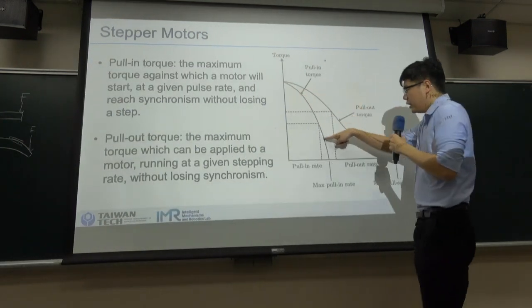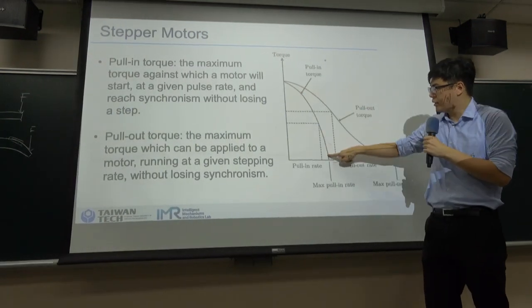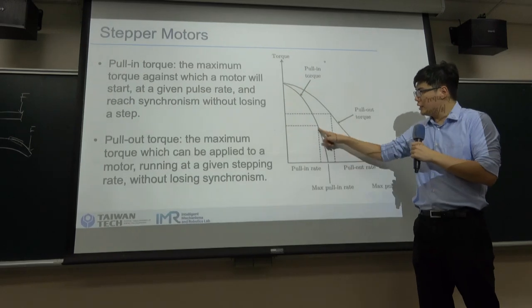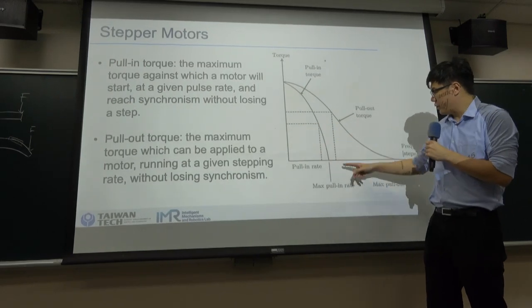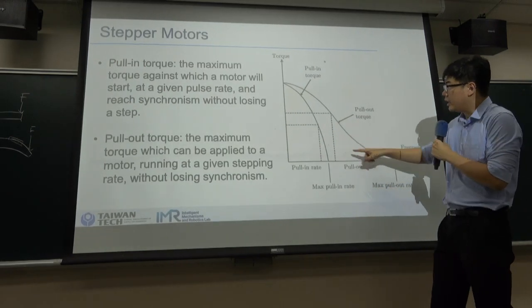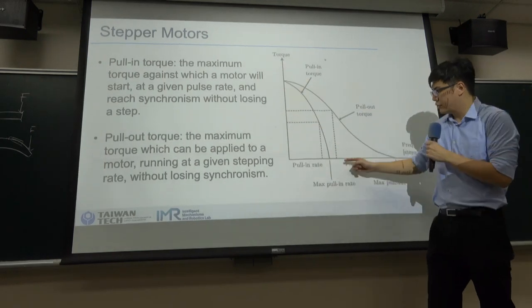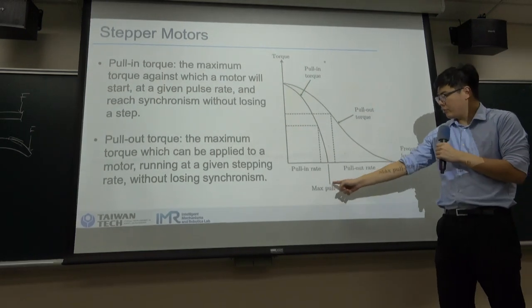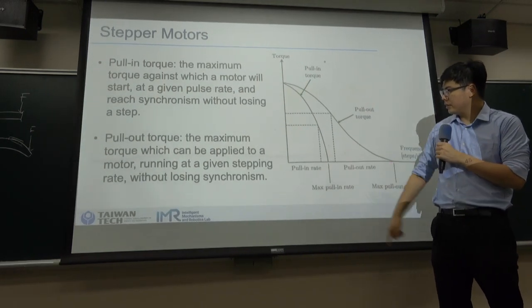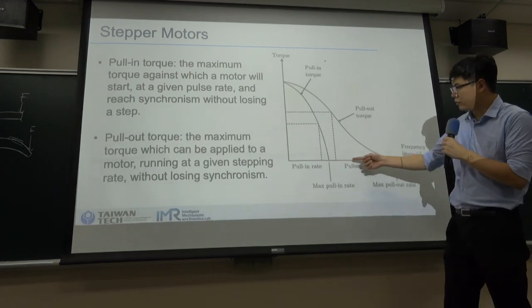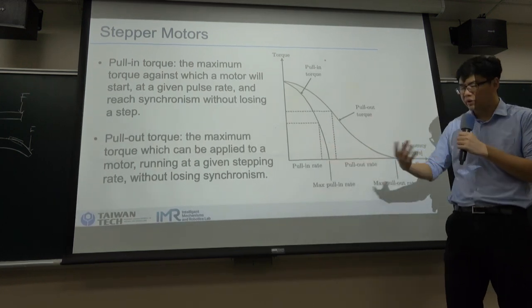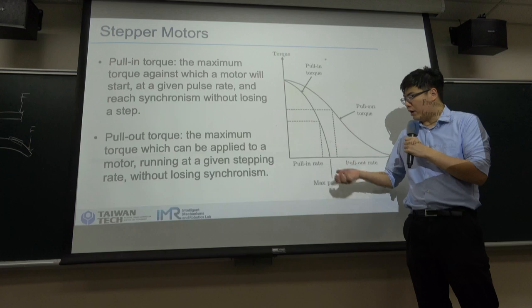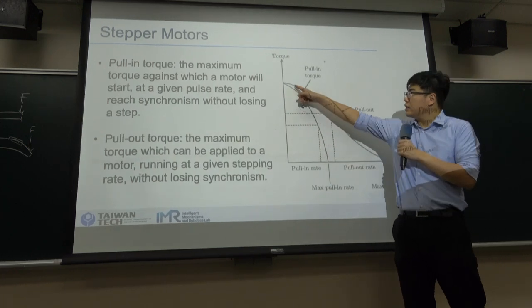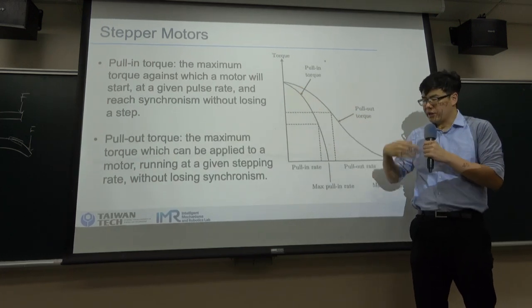You can see the pull-in torque line here on the graph, and this is the pull-in rate. Here is the speed of the motor, and here is the torque. This is the maximum pull-in rate, it depends on the speed you want the motor to drive at. So this is the maximum torque you can use to start this motor.